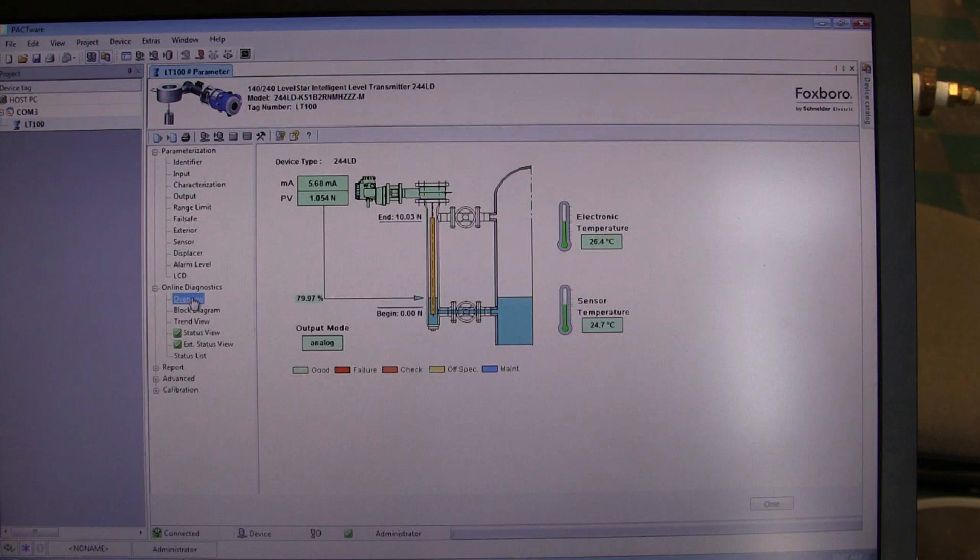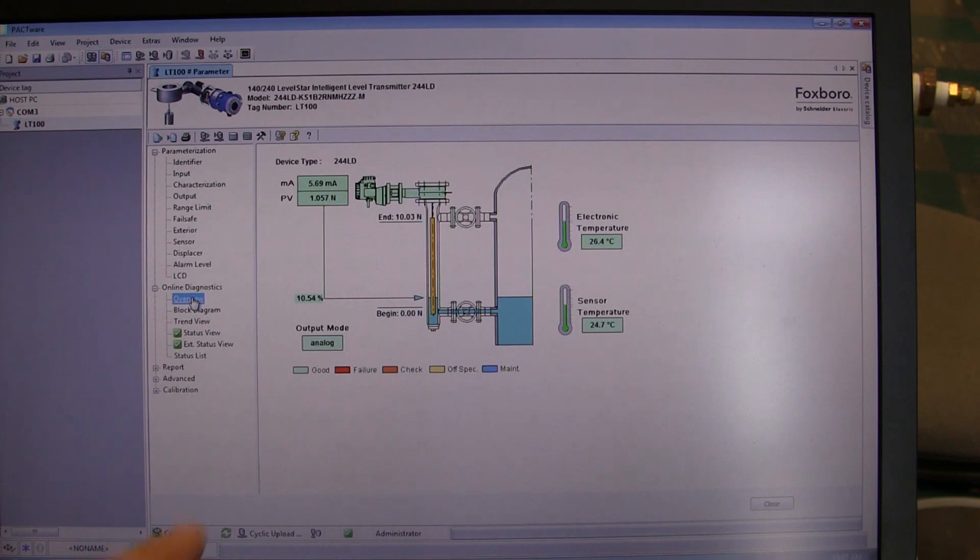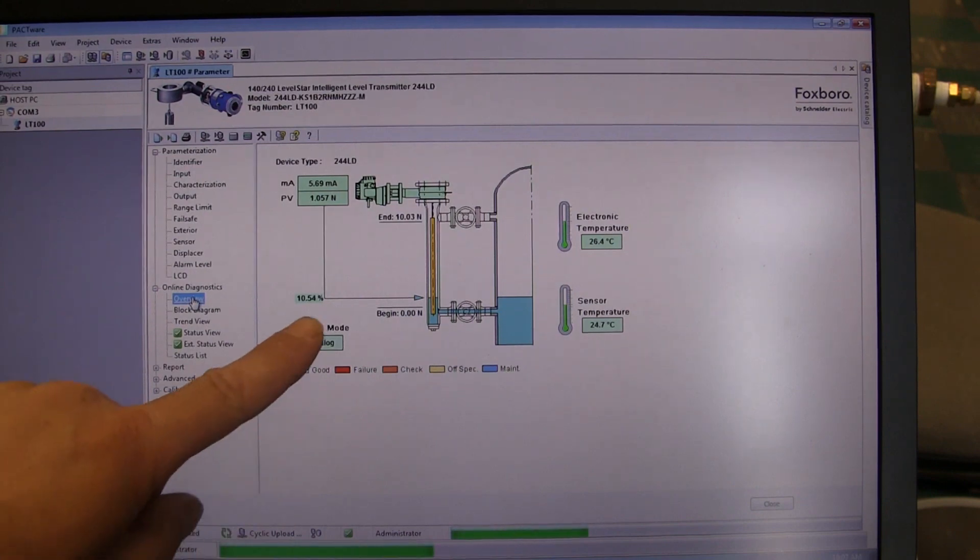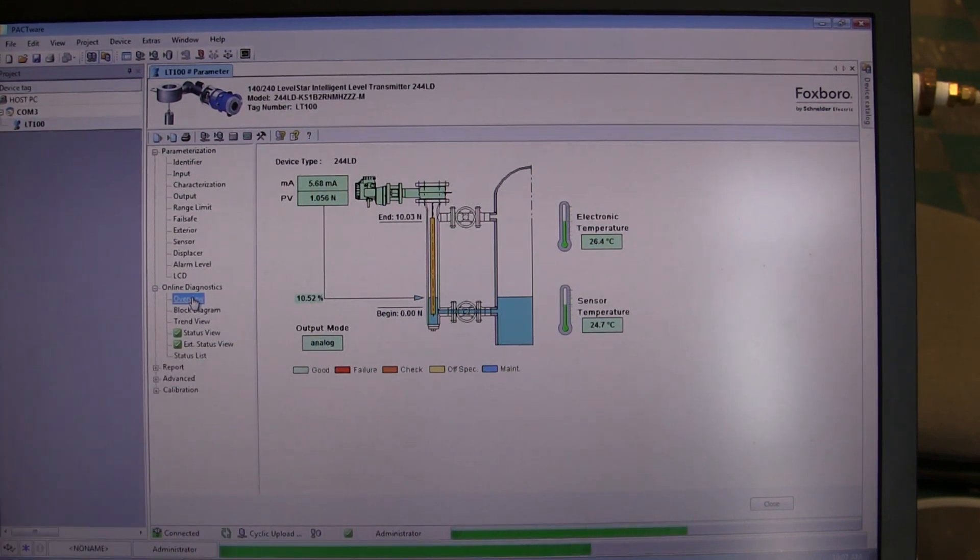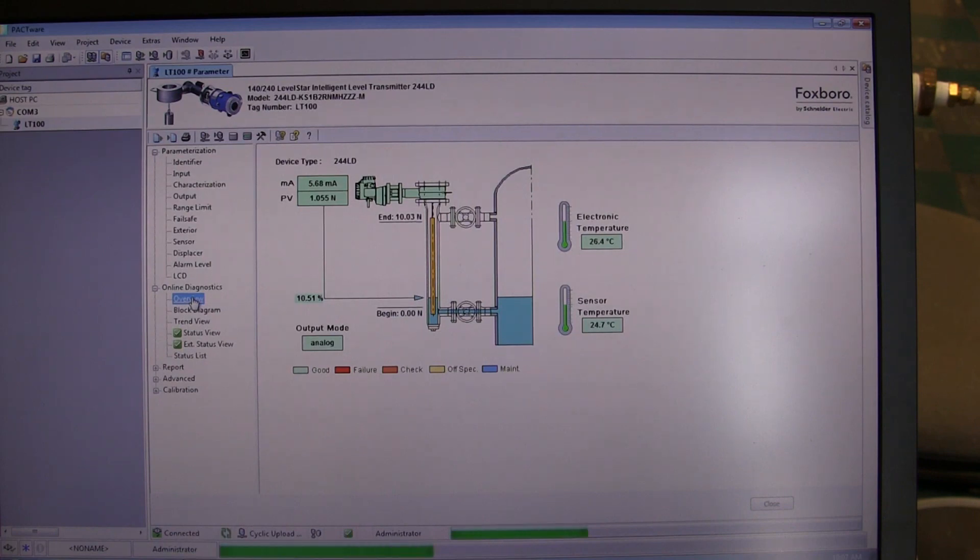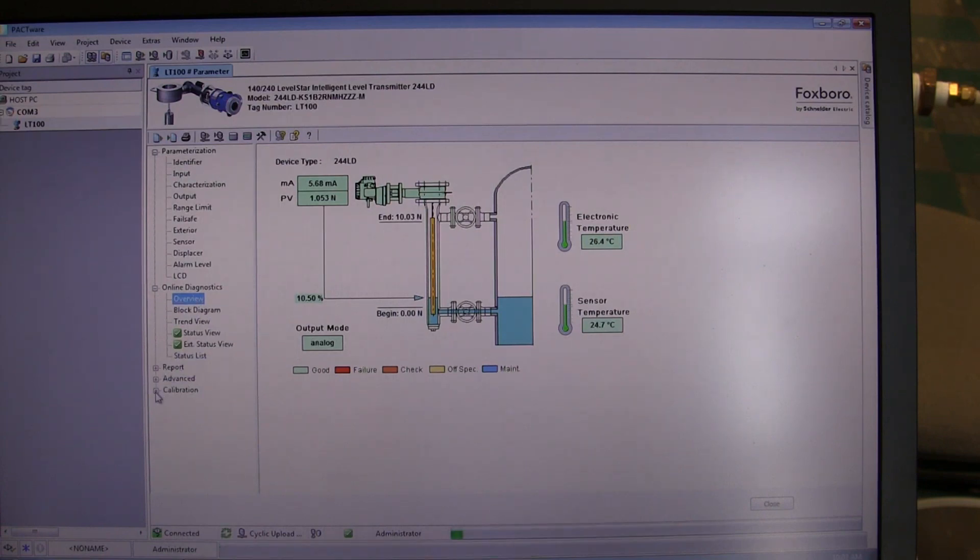Observe what the actual PV value is. You will see that right now the PV is indicating 10.5 percent of span. At this point, our tank is empty, so what we want to do is simply zero out the transmitter.